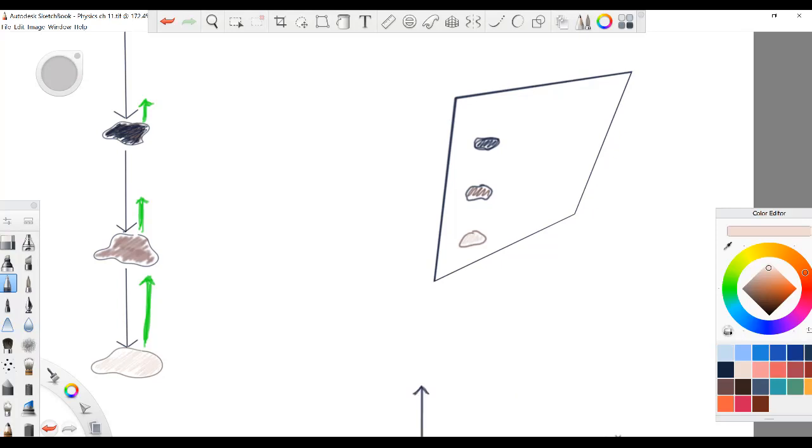Echoes came back. The echoes were processed. They said this one took 13 microseconds. That's 1 centimeter deep. The first one, 26, 39 microseconds, whatever. And we've placed our echoes on the screen according to the time it took. Now, that's one aspect, is time. The other aspect is how strong each echo was.